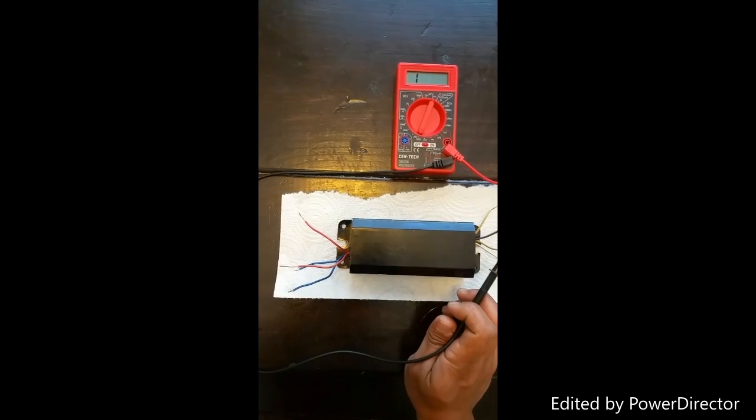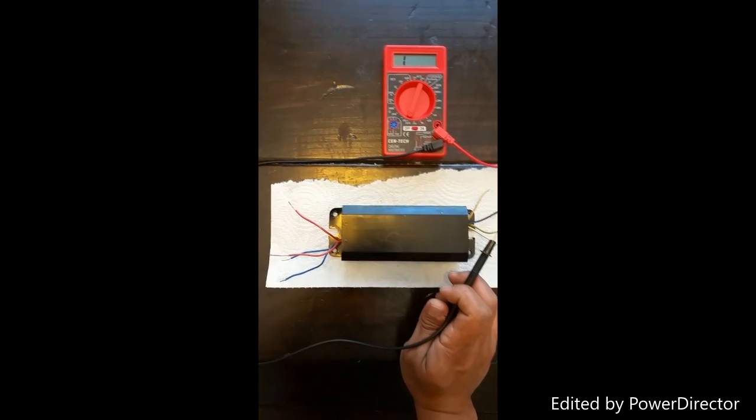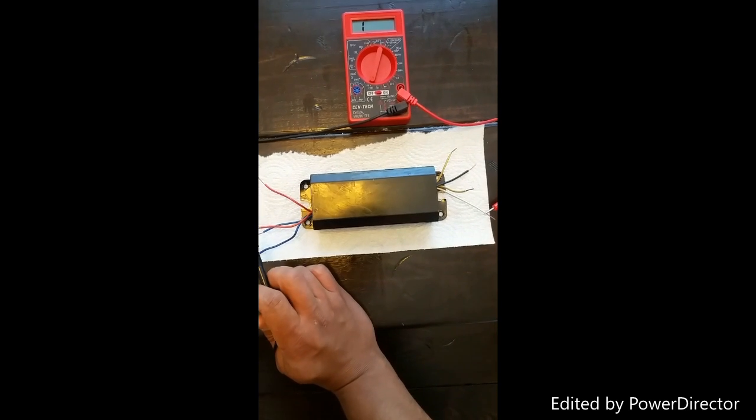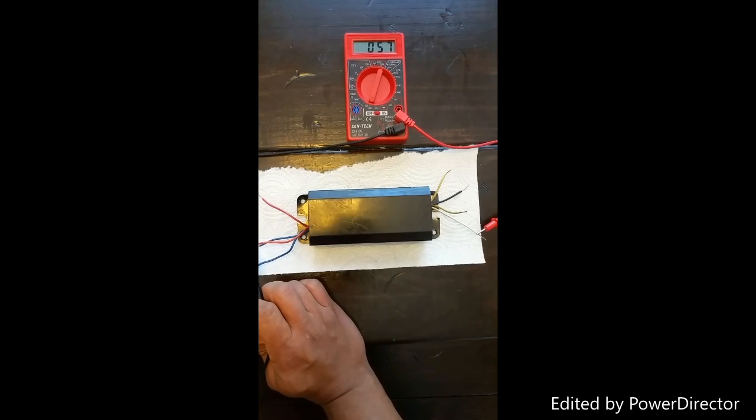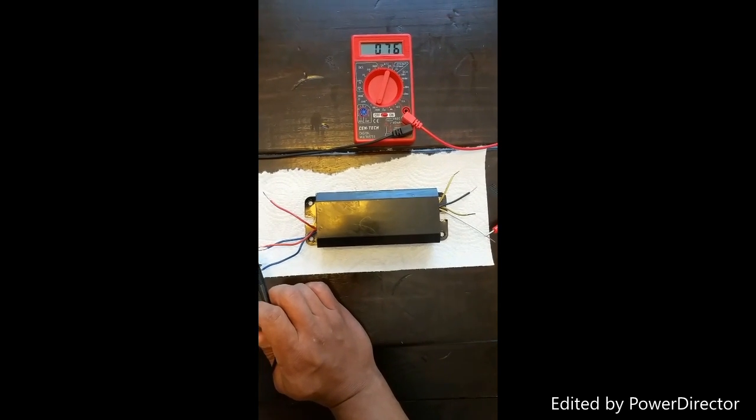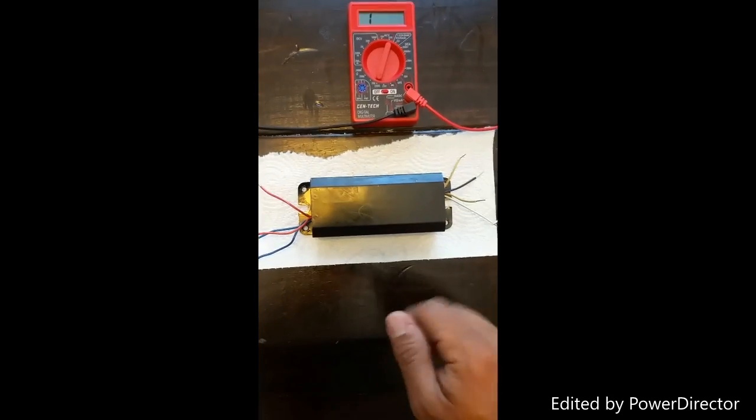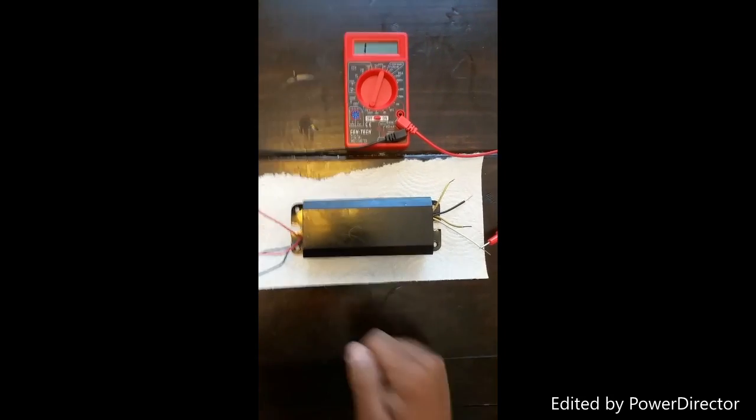Again, if you test a line and you see no change or one, that's indicating an open line. But once you go to the one that has resistance, you can see on the multimeter that that one is bad. Telltale sign that you'll need a new ballast here.